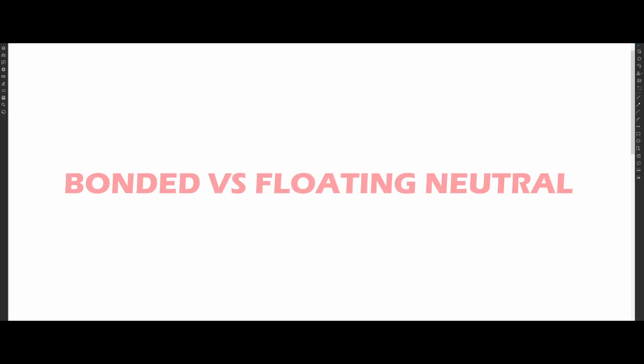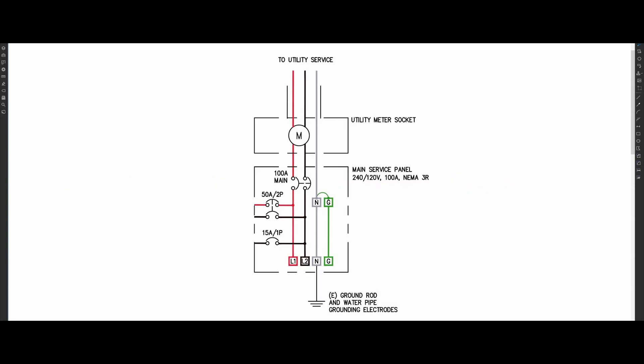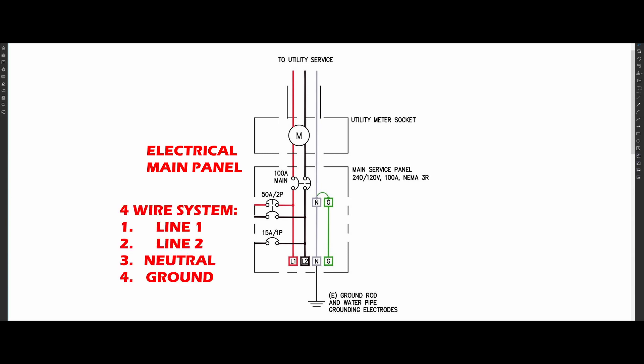Before we begin, you need to understand the difference between a bonded and floating neutral generator. Inside the generator, there are four bus bars similar to what you would have at your main electrical panel. I have color-coded them. This is a four-wire system: line 1, line 2, neutral, and ground.